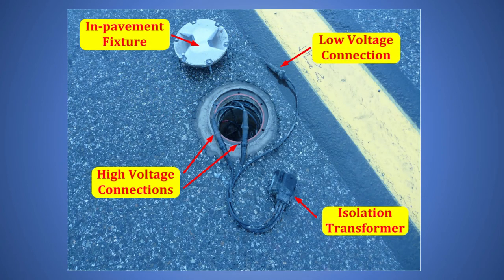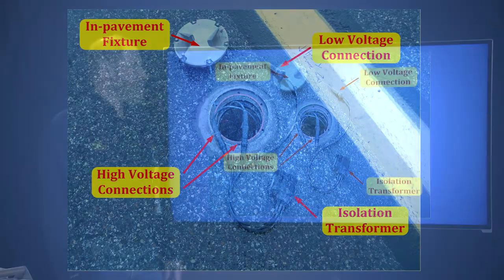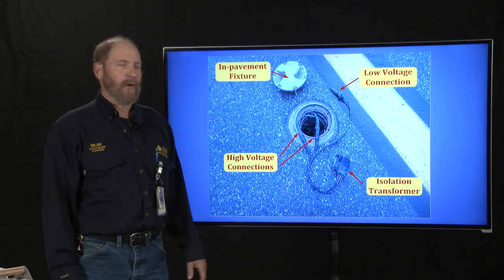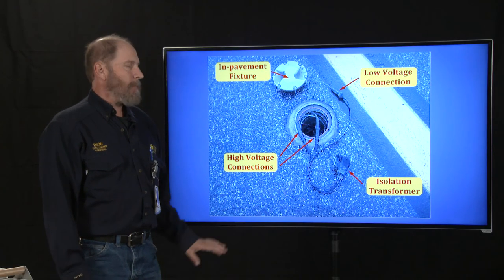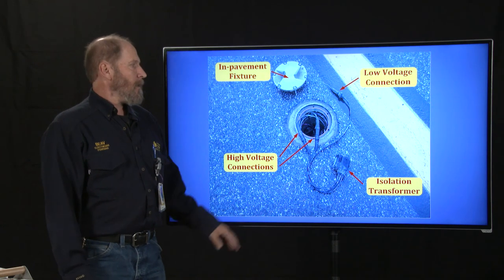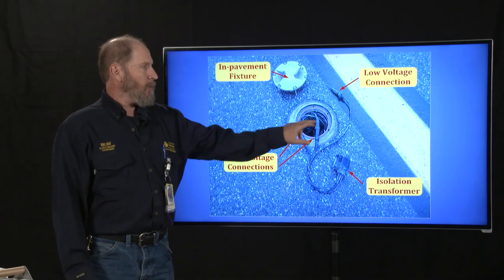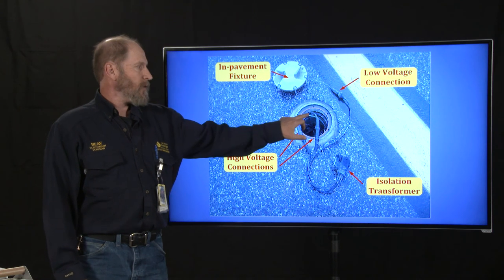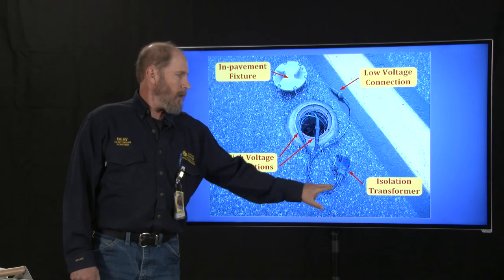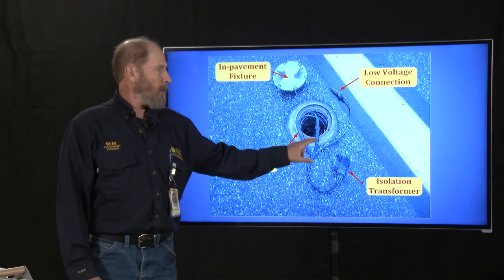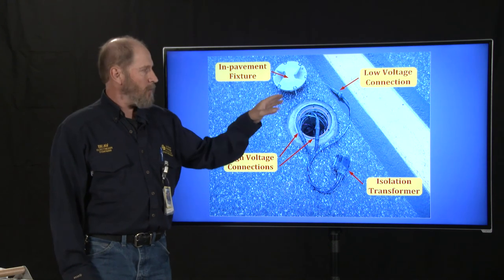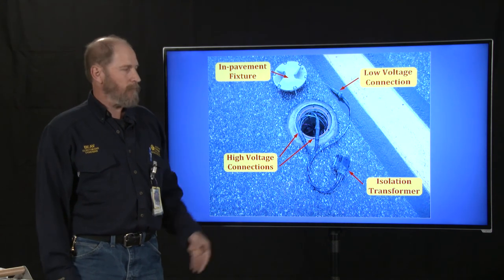Now from those lighting vaults, it goes out to the individual circuits. So this is a typical runway centerline circuit, in-pavement centerline. It's a very simple system. Our wiring comes in on our primary voltage here, our high voltage wires, they come out, they go through our transformer, back out another wire, and it goes on to the next fixture.